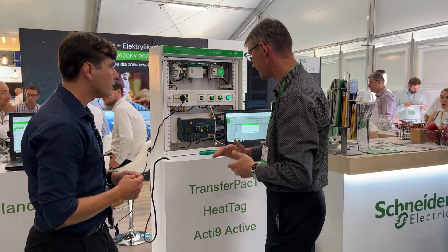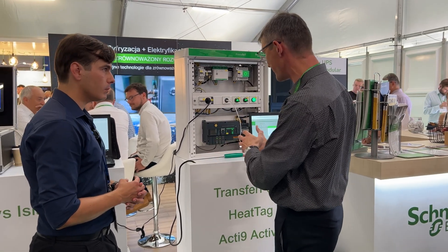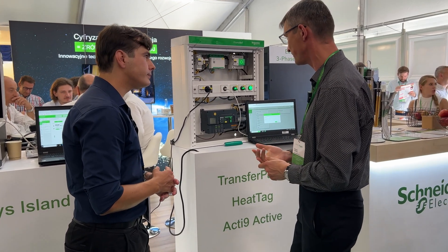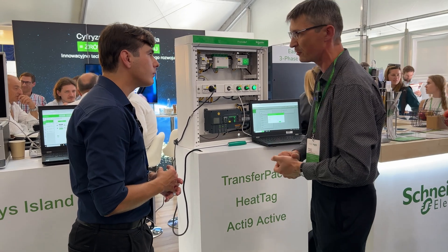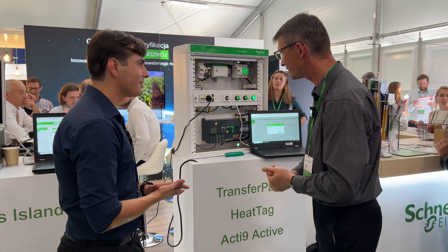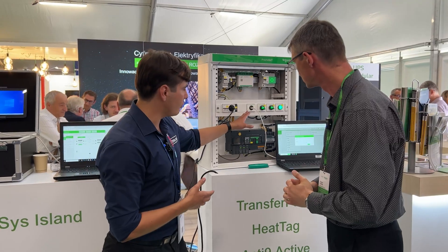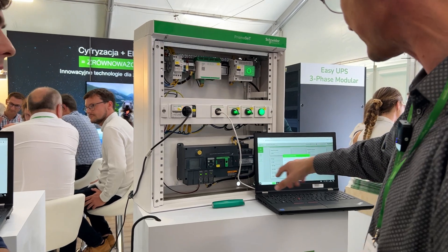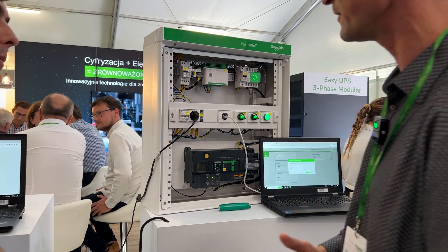This is our latest launched product for switching between the basic power supply and the backup supply. It is a compact, all-in-one design for cases where we need backup supply for small commercial buildings mainly. This works fast and automatically? Yes, we can make some adjustments so that it fits better to our installation. There is also an ethernet connector so you can modify it — this connects to the panel server, allowing direct computer communication, but also connection to any BMS that uses Modbus TCP.